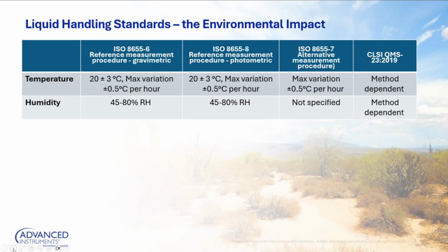So the environmental impact comes into play especially for air displacement pipettes. Part 6 and Part 8 indicate that your laboratory temperature should be 20 degrees Celsius plus or minus 3 degrees, with a max variation of 0.5 degrees Celsius per hour. So if you have a highly uncontrolled laboratory environment, maybe you're the first person to enter the lab in the morning, it's very cold, and then as your colleagues enter the lab, the temperature increases, and you can see that temperature differing once you have 20 bodies in the lab versus no bodies in the lab. How fast is it differing? That can affect how these pipettes perform.